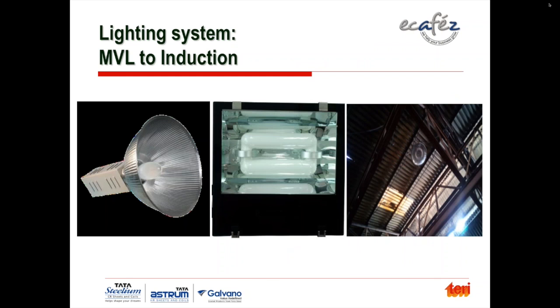The final case study is about lighting. This case study is basically the use of induction lamp instead of mercury vapor lamp, essentially for outdoor lighting, sometimes also for indoor lighting within the plant. Now, these are the fixtures. The middle one is the induction lamp, a very high efficiency lamp, a bit expensive. Typically the mercury vapor lamp here is 250 watt rating, whereas the induction lamp of equivalent lumen is 150 watts rating. So straight away 100 watts can be saved.